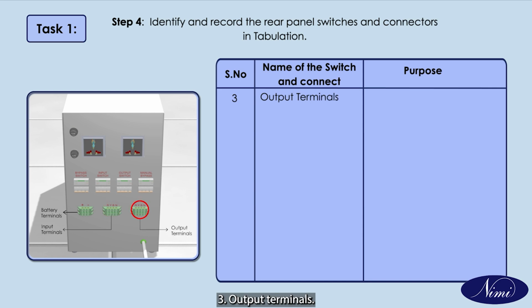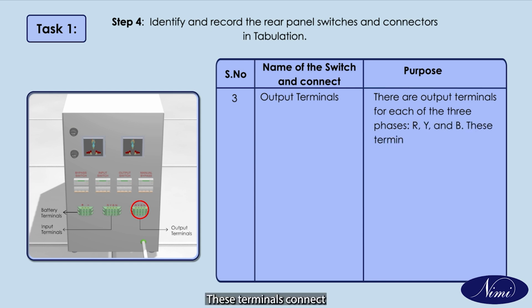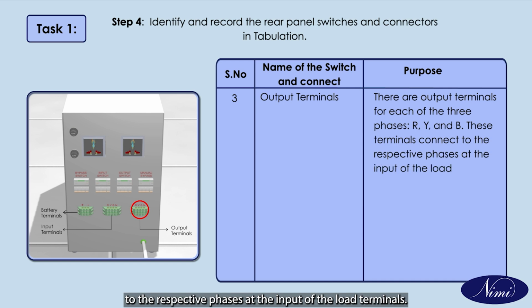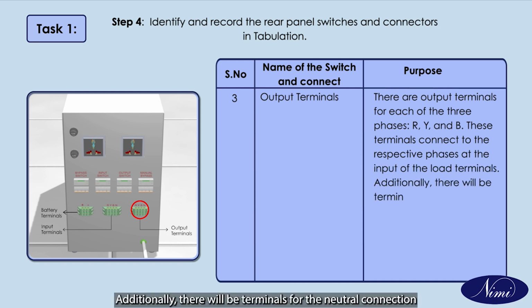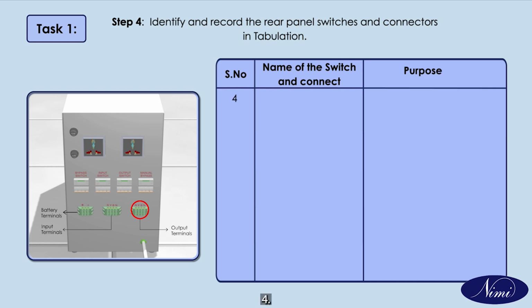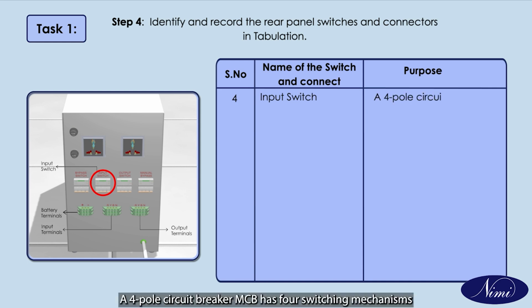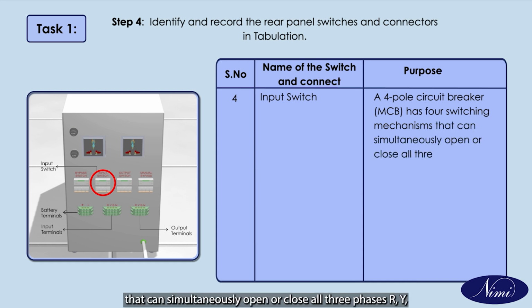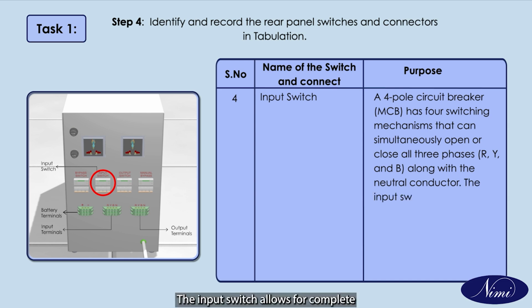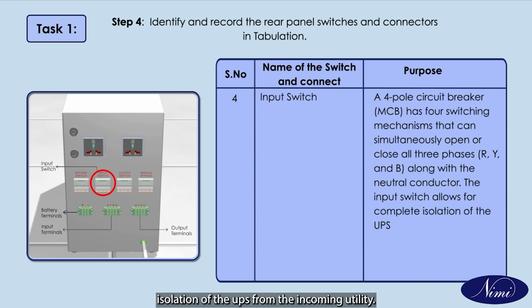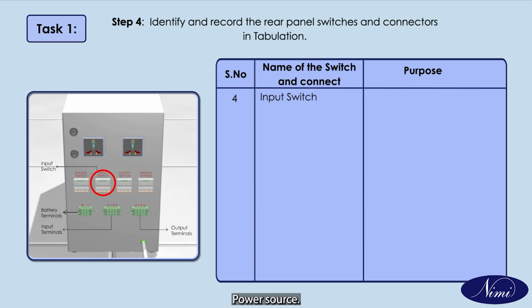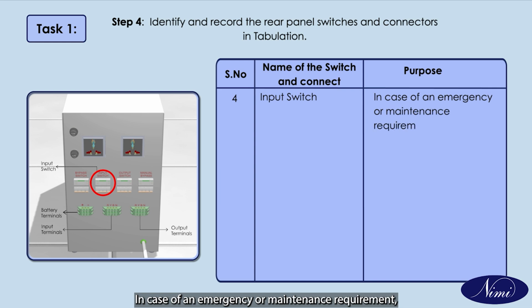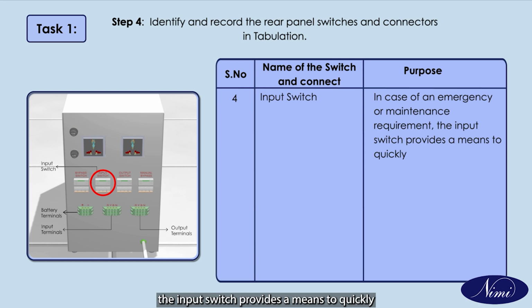Number 3. Output terminals. There are output terminals for each of the three phases R, Y and B. These terminals connect to the respective phases at the input of the load terminals. Additionally, there will be terminals for the neutral connection N. Number 4. Input switch. A 4-pole circuit breaker MCB has 4 switching mechanisms that can simultaneously open or close all three phases R, Y and B, along with the neutral conductor. The input switch allows for complete isolation of the UPS from the incoming utility power source.